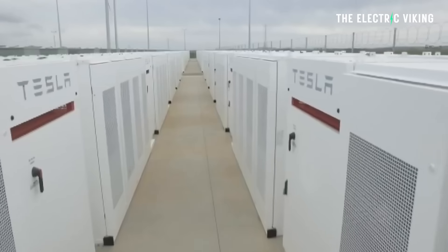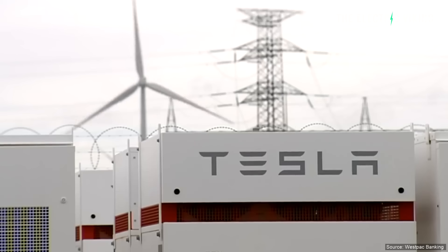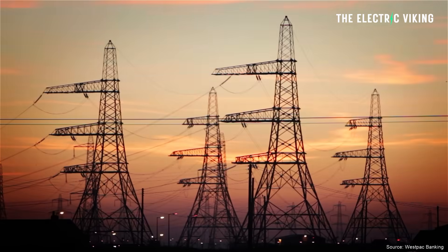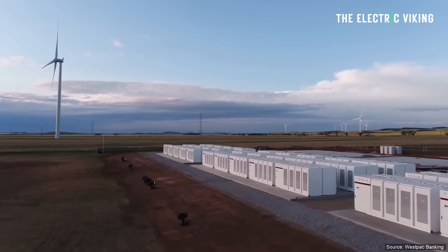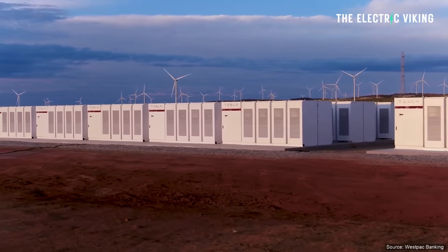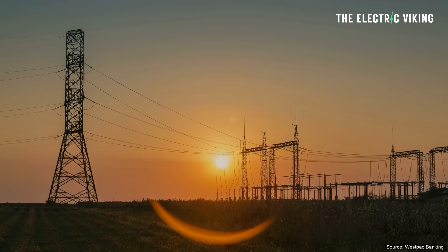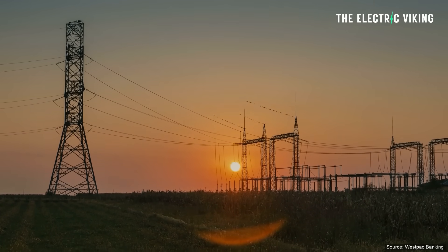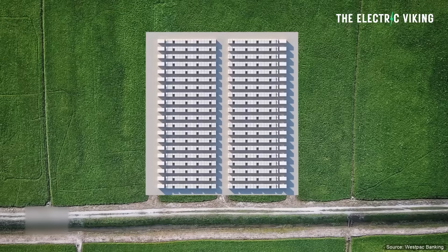The new battery will provide grid stabilization services using Tesla's advanced grid-forming inverter technology, which can operate in a virtual synchronous generator mode, mimicking the synchronous nature of traditional fossil fuel and hydropower generators — but doing it much better. Peaker plants take about half an hour to respond on average, while this battery pack can respond within 60 seconds to increased grid demand. With batteries like this, you avoid blackouts on the hottest days of the year.